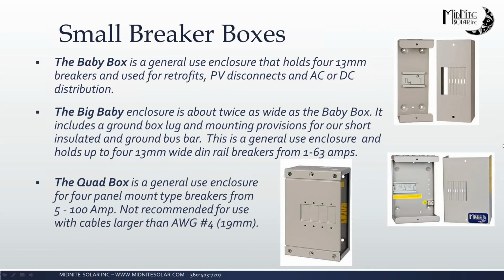We have a full line of small breaker boxes. These are great if you just need a little space to put a couple of PV breakers or some AC breakers. They're very simple to install and don't take up a whole lot of space. The baby box is large enough to hold 4 of our breakers, and it's great for using for retrofits, PV disconnects, or AC or DC distribution. It should be noted that this is not an ETL listed box, so if you do need that, then you would want to upgrade to the big baby.